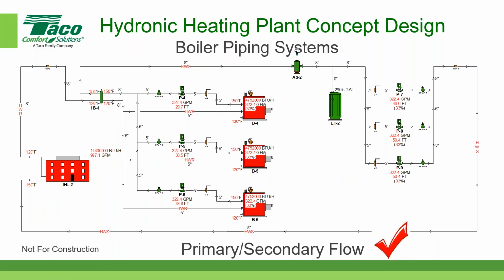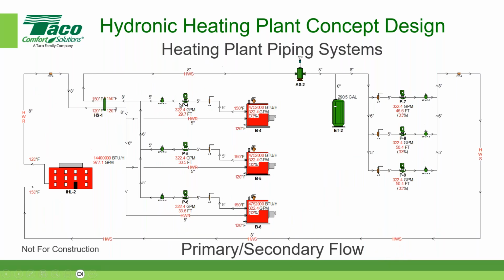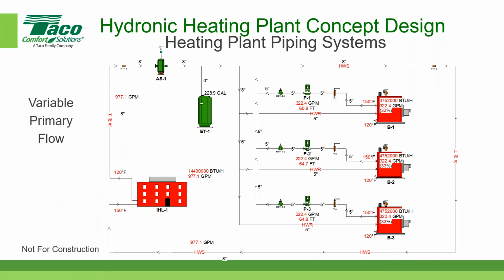Going back to the variable primary design, based on the diagram, is it more important to locate the air separator and expansion tank at the lowest pressure, not the highest temperature, like in a primary secondary design? Does that make sense? Well, in general, there's a trade-off, because sometimes it's more convenient to place the air and dirt separator at the higher temperature. It all depends on the relationship between the temperature and the pressure.